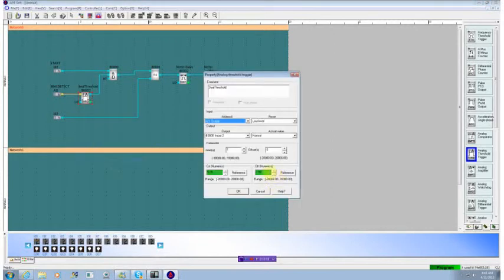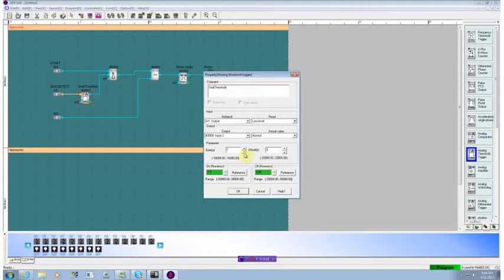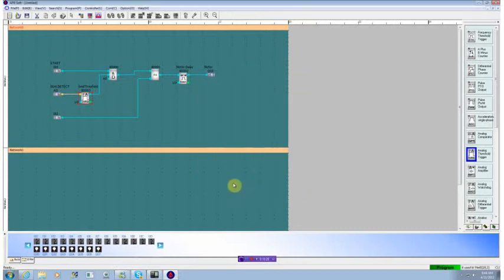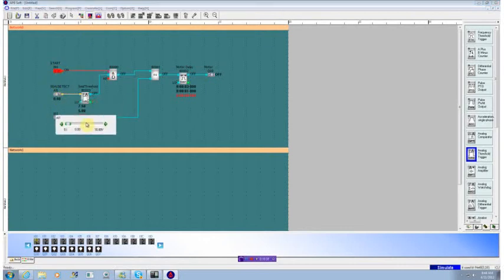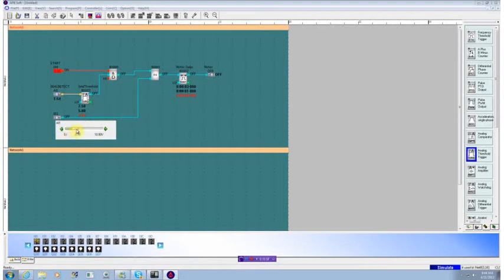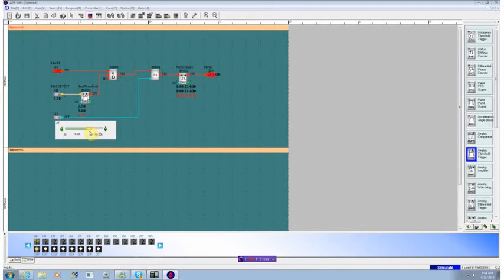But what we really wanted to do is have it act slightly differently. So we'll go into the property section. We'll change this to an off at five. We want to turn it on at seven point five. Now when we run our simulator, and we hit this, we see that as we increase it, nothing happens when we hit five. But when we hit seven point five, it turns on. We stay on until we reduce that signal down below five. It turns off. So we've now got a hysteresis effect on our analog input.